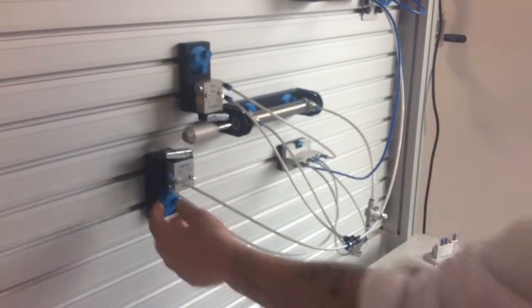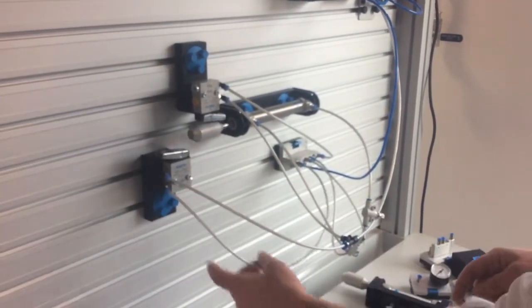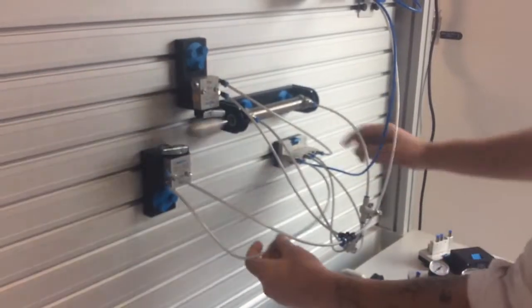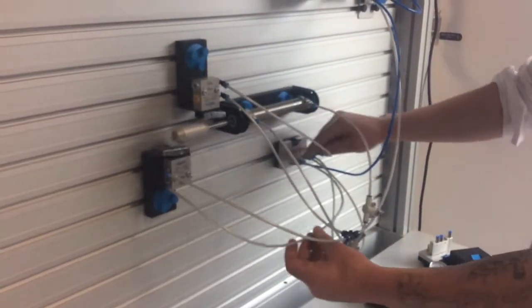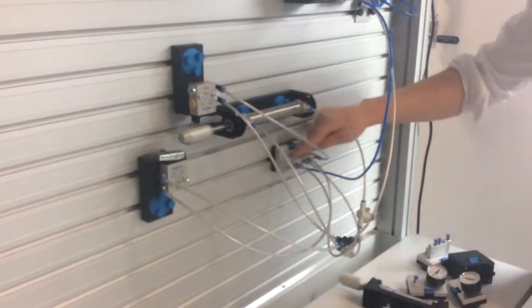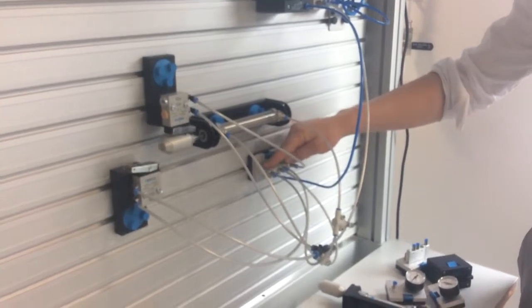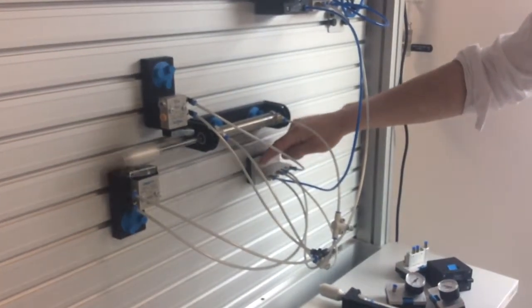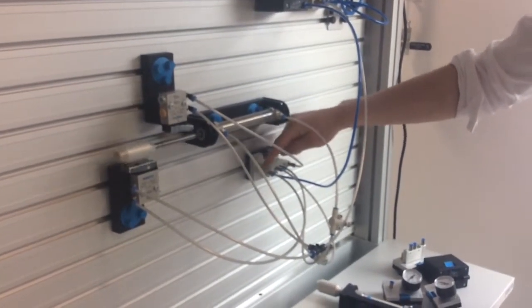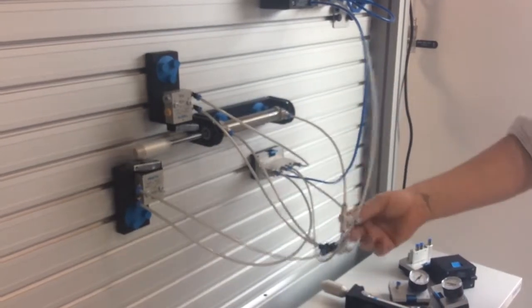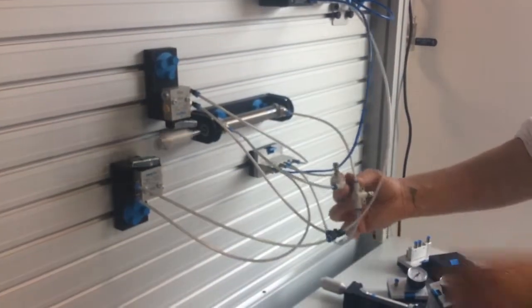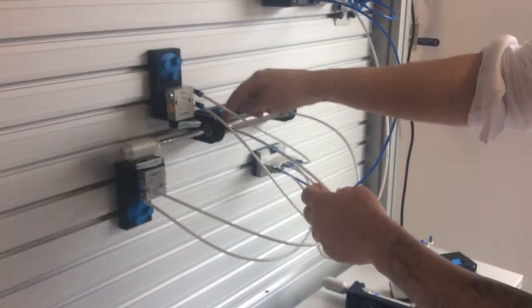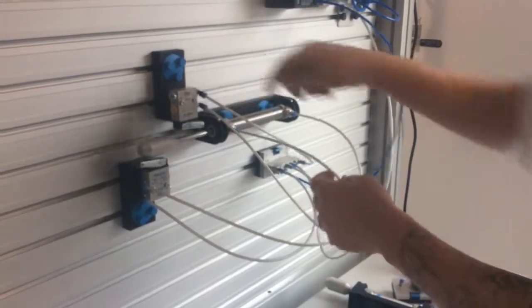It will open up the bottom of the limit switch to allow this pressurized air into the left-hand pilot of our 5-way 2-position 5/2 valve. So, left-hand pilot air pressure moves the shuttle across, applies pressure to this end of the cylinder.